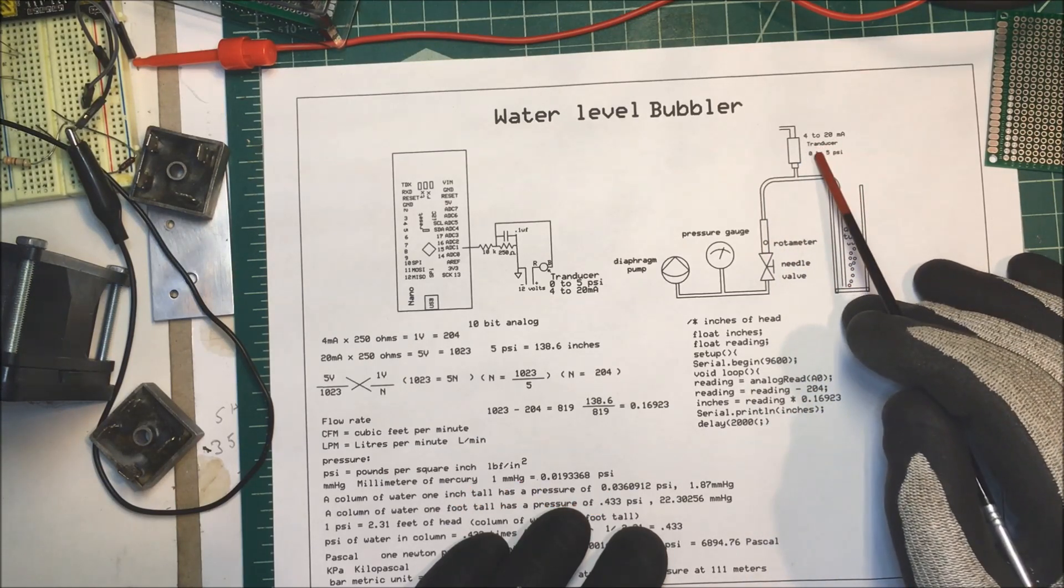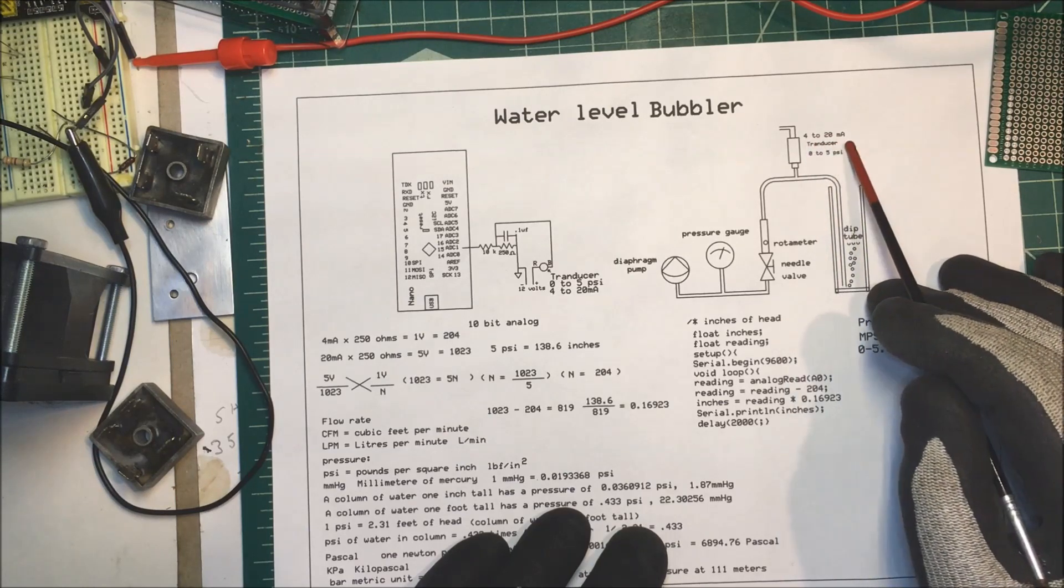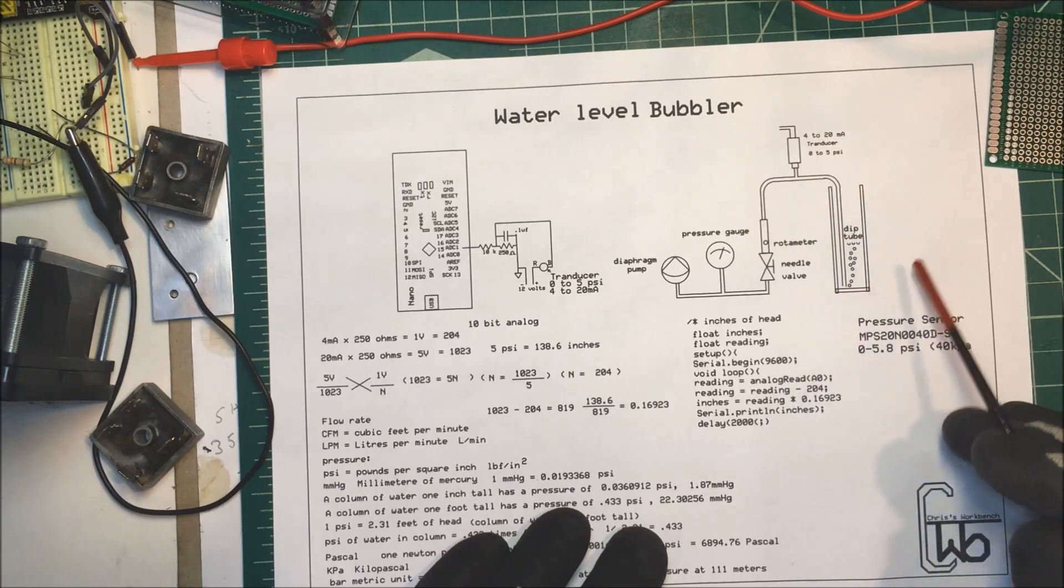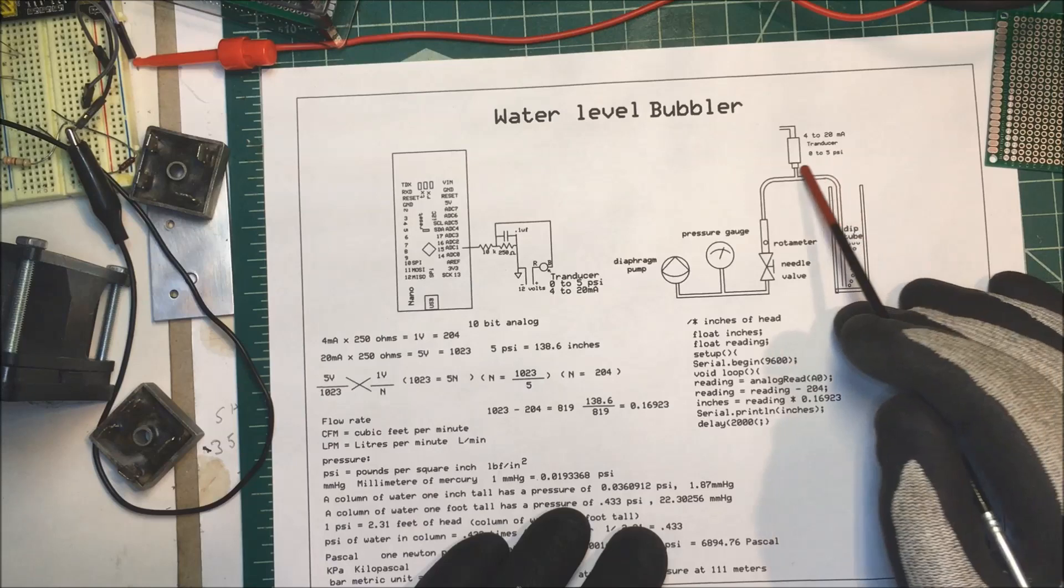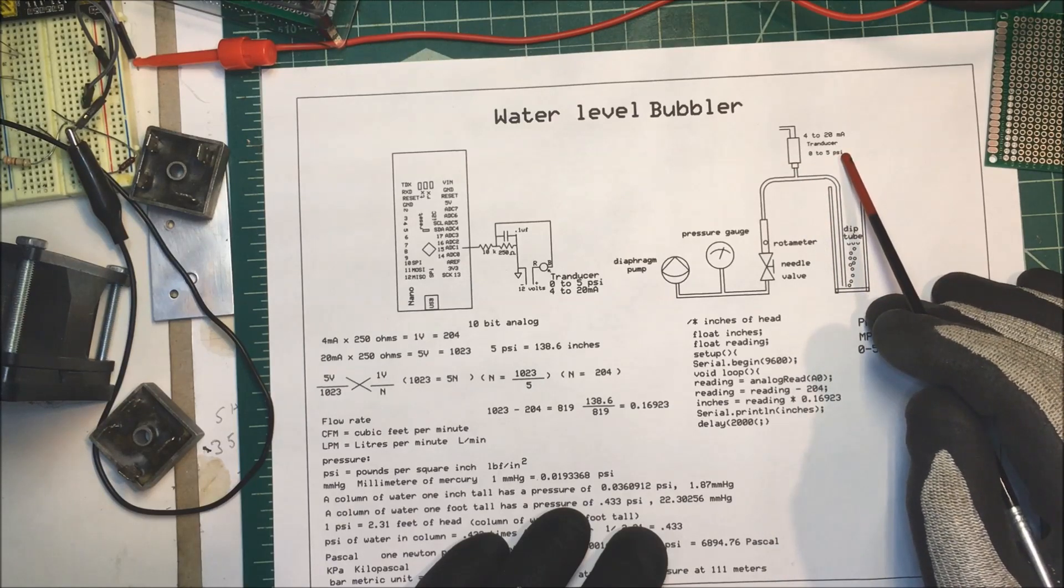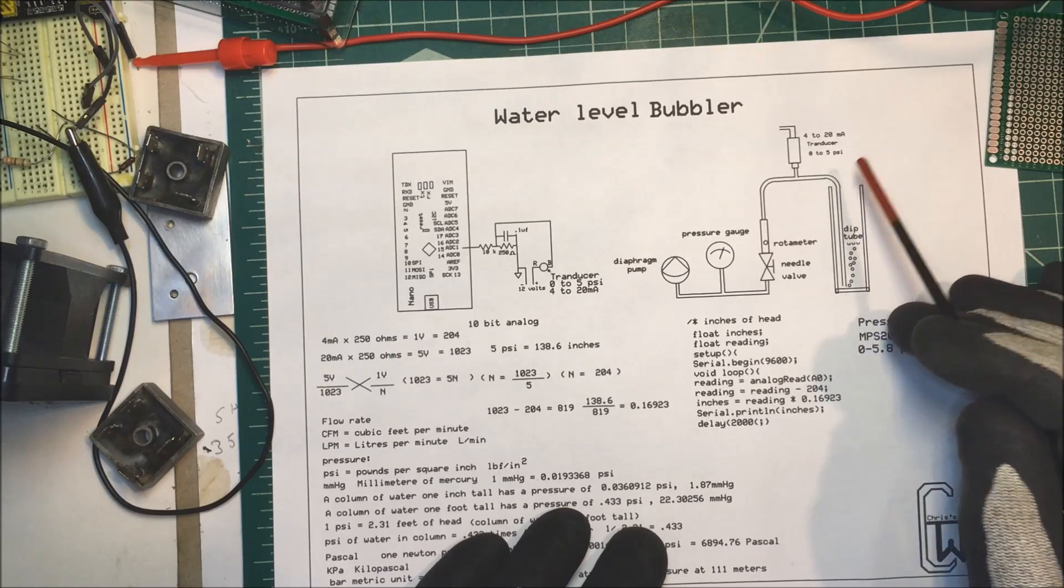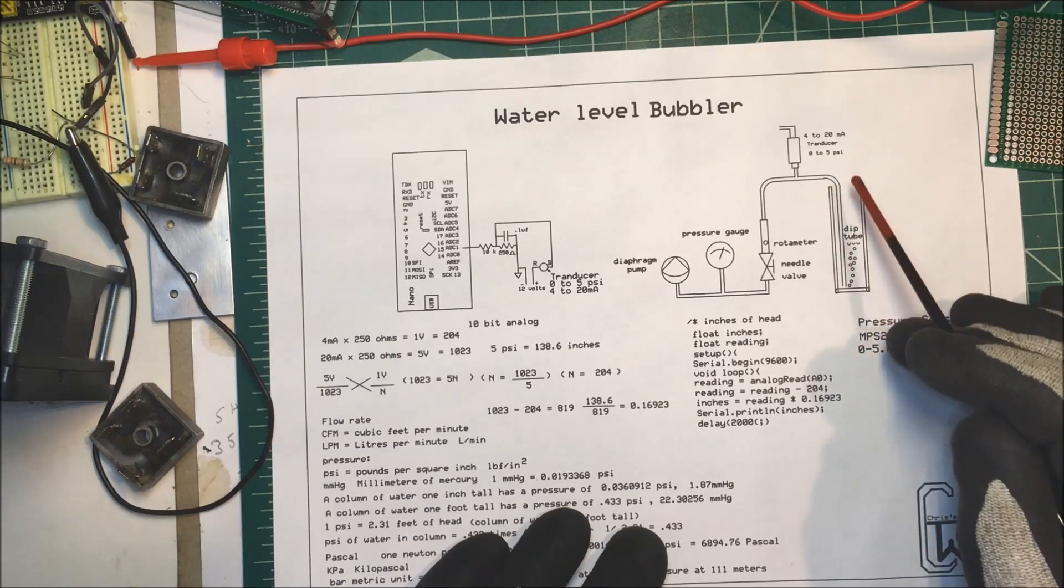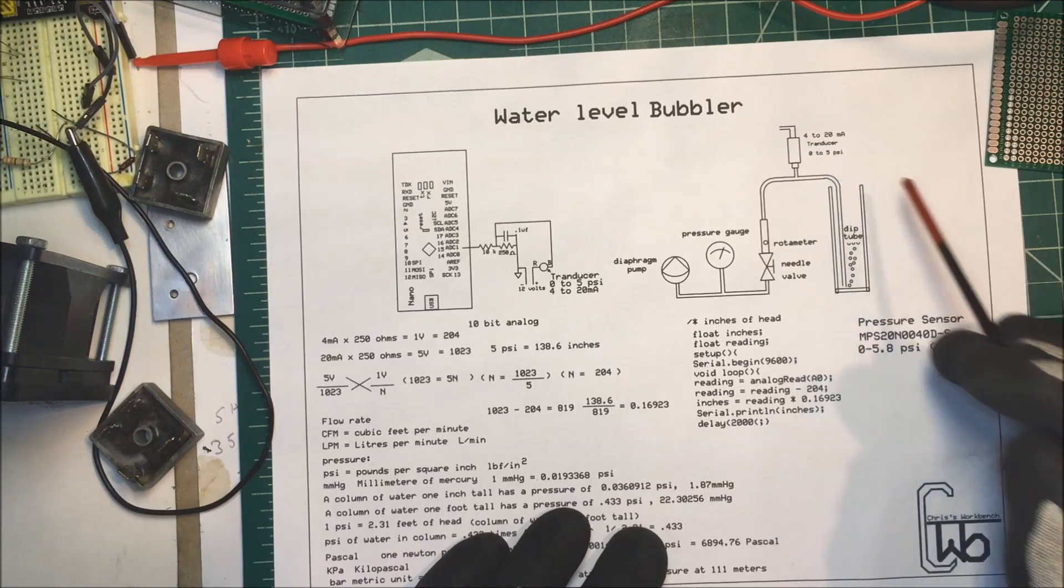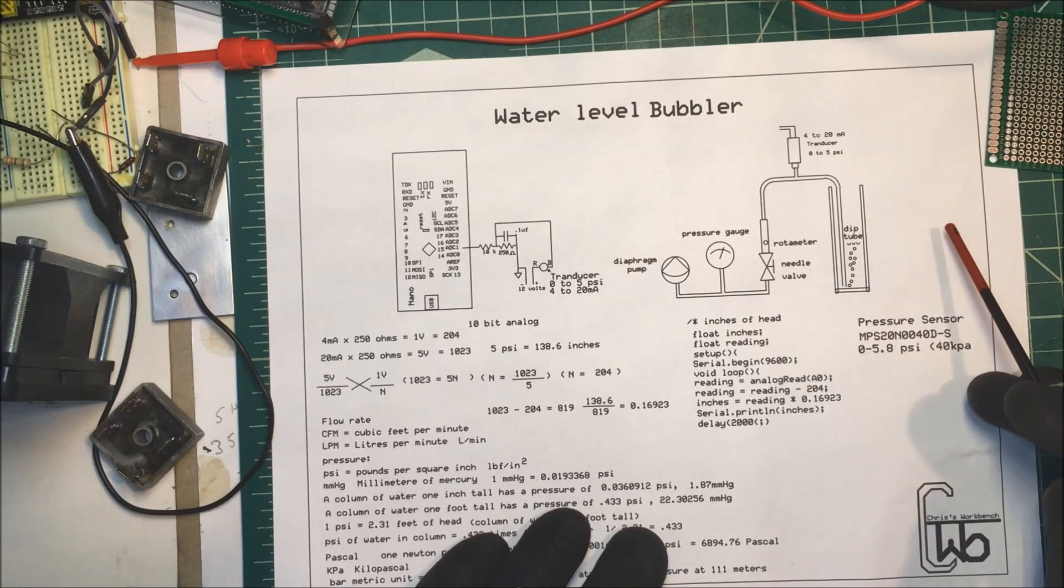And then we have a transducer. In this case, I'm using a 4 to 20 milliamp transducer, 0 to 5 psi. At 0 to 5 psi, that'll get a tank of water that's about 11 foot tall. And so if you need to, if the well's deeper than that, then you need to have a higher psi transducer.